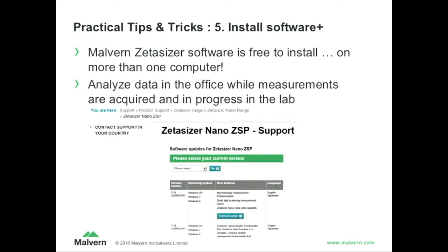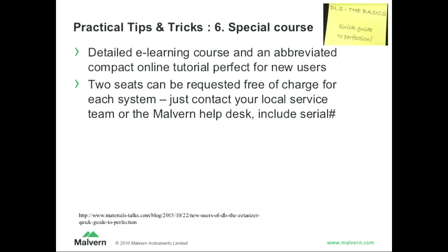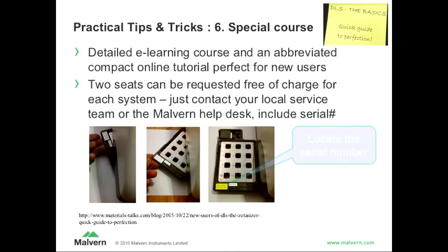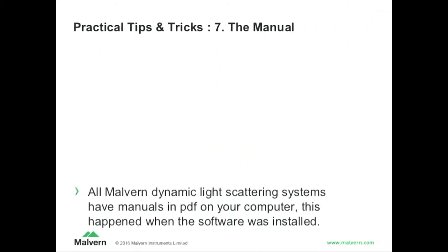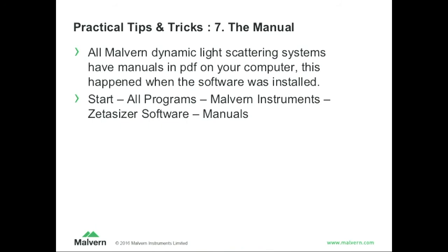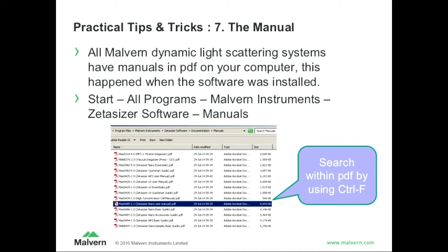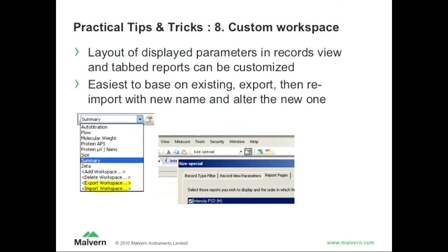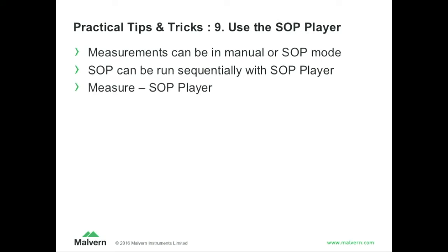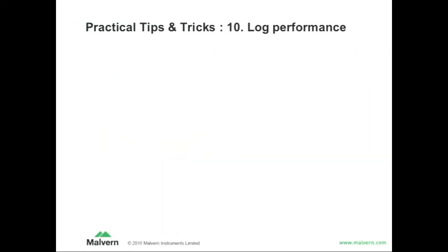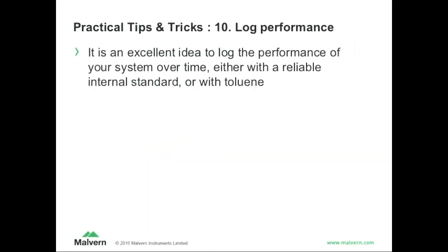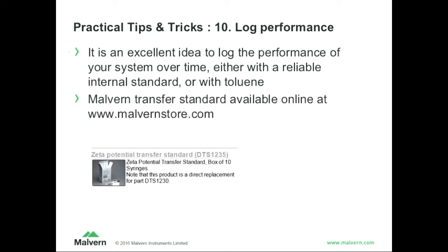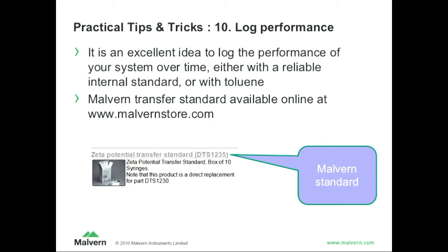You can install the software on as many computers as you like — don't worry about licenses, just download it from our website. We do have some e-learning, and there's a free one-hour tutorial on the blog. If you have new users using the system, tell them about it. There is a manual — surprisingly not many people read the hard copy — but there's a PDF version, and what I like about PDF is that you can press Ctrl+F and search for what you're trying to find. You can customize the software to put workspaces in there to make your own liposome or nano-assembler workspace. You can use SOP players to concatenate different SOPs so you can make more complicated setups, maybe combining zeta potential and size measurements. And one thing not many people do but is a nice thing: keep a log of what your system is doing as a function of time — as a little standard. You can also use your own internal reference and keep track of what your system is doing.